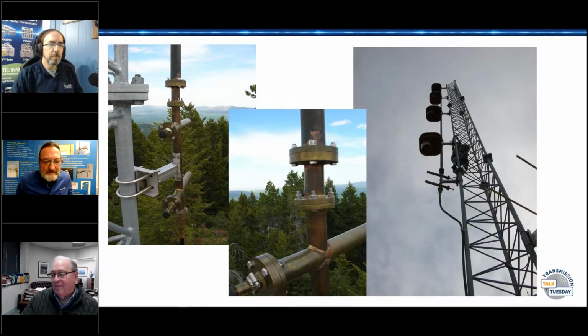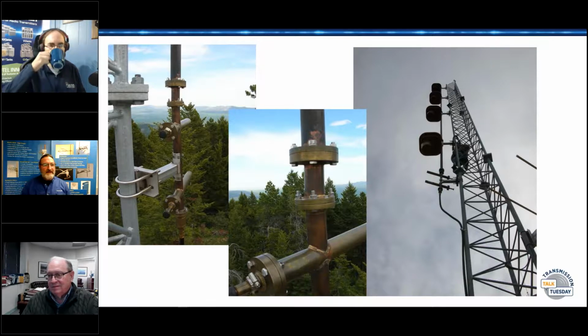Sean, I interrupted you, go ahead. No, I was going to speak to FM installations, but that idea of monitoring the indications, it's never too late to establish a baseline of the operating parameters of a system. The best time is during installation, so you have right out of the box manufactured, approved installation parameters, and that's your benchmark. Anything different from that is going to be either an indication of just normal swings in the performance, or an indication of something going bad. But it's a great way to establish a comparative measurement that you can look at over time.